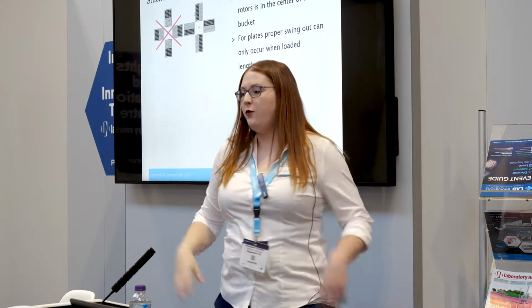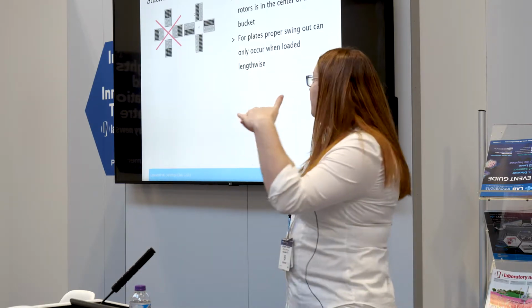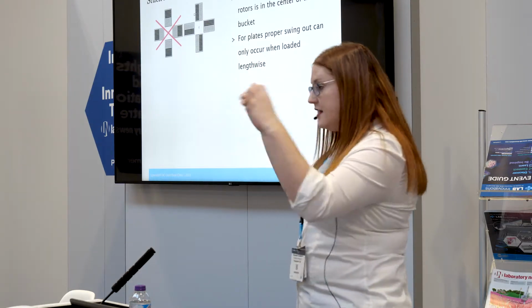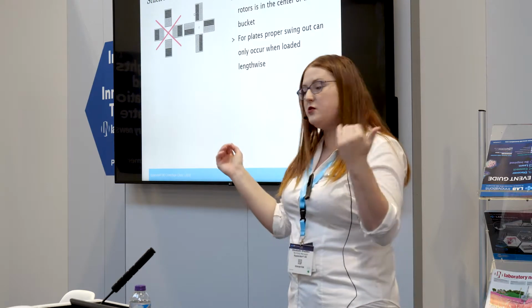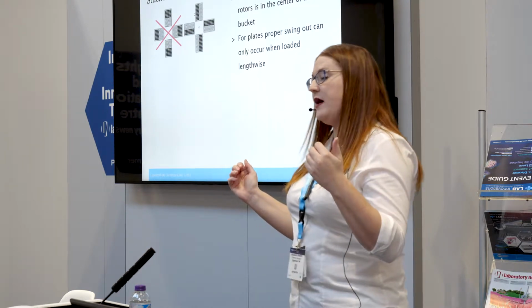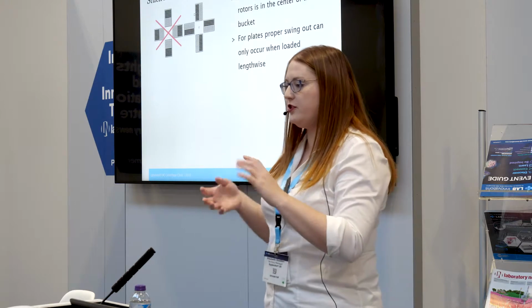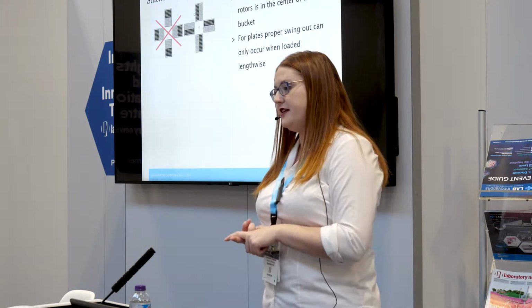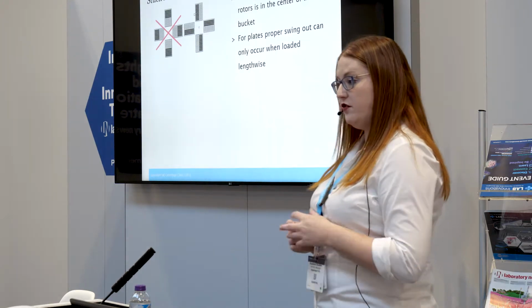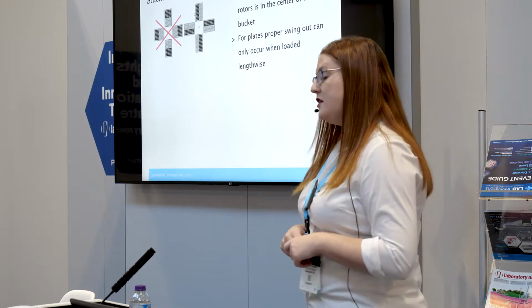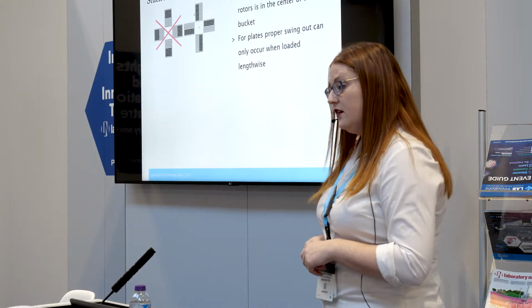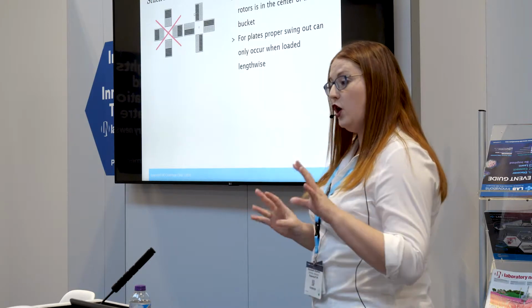But when the buckets swing out horizontally, all of the weight is going to be in the top of the bucket, which means it's not going to swing out properly, and it's not going to be balanced properly, and that's going to apply torsional forces to the cross section of your rotor, and over time it's going to damage your rotor. So your centrifuge would probably not pick up on that, it probably wouldn't complain, but it will knacker it over a long period of time.